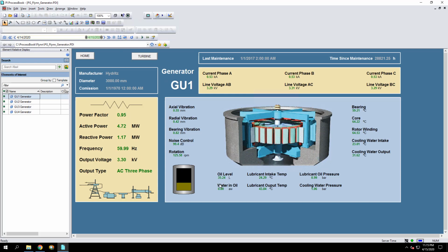And we want to look at the oil level next to the bar symbol here. Again, similar to the last question, we are going to click through each generator to see which has the lowest oil level, and generator 4 has the lowest level at 32.5 liters.